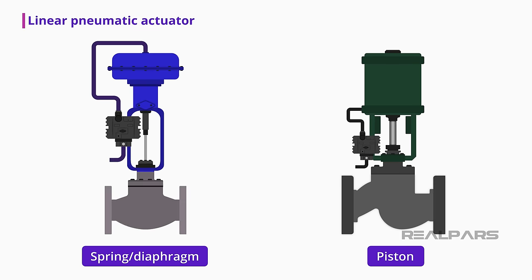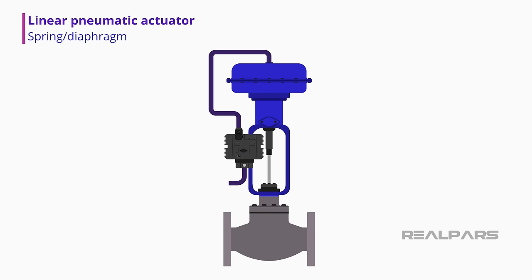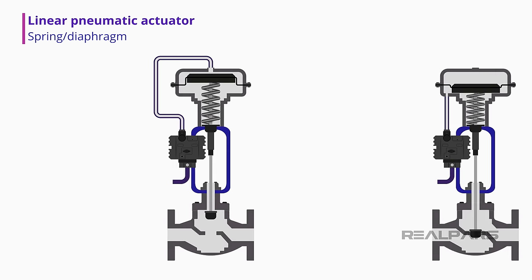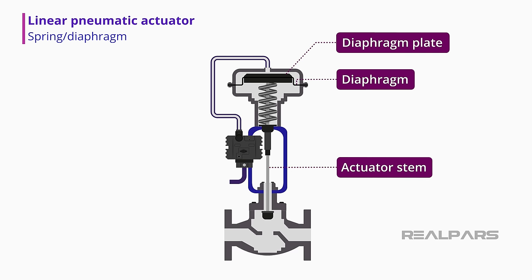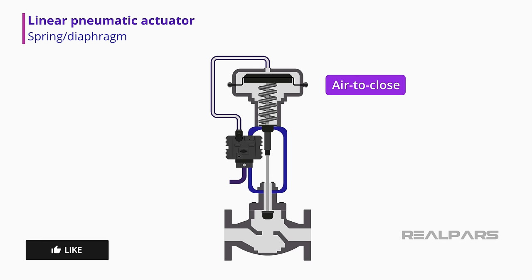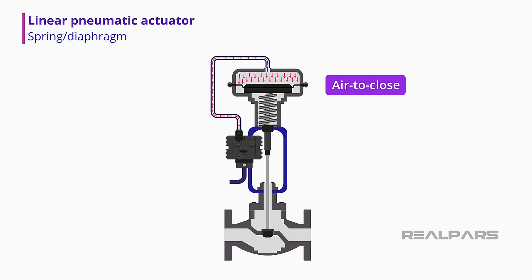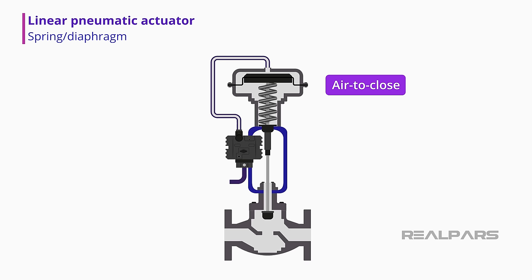The spring diaphragm pneumatic actuator is probably the most common actuator used to operate industrial process control valves. It consists of a diaphragm and plate that are connected to an actuator stem. A flexible diaphragm is enclosed in a pressure-tight housing. Pneumatic pressure enters this housing, applying pressure to the diaphragm. As the air pressure increases, the force exerted against the spring increases, causing the actuator stem to move. Reducing the pneumatic pressure will cause the spring to retract the diaphragm, and the actuator stem will move a valve in or out of a valve body.